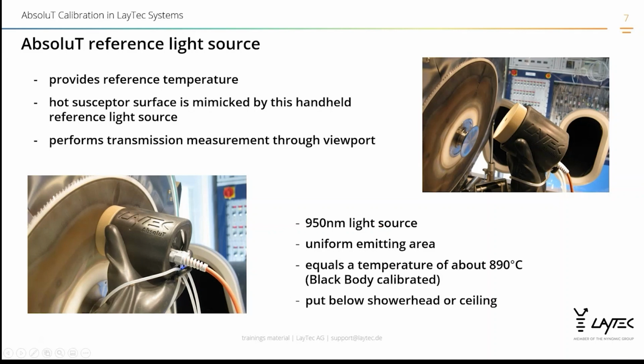We will go in the second part of this video to our test stand lab, and we will demonstrate this live and show all the tips and tricks to perform and prepare this calibration. Here just a quick preview. That is how the front side of the AbsoluT tool looks. There's an exit slit, and that exit slit diameter is much wider than the EpiTT light spot, which passes the ceiling or showerhead viewport tube and is focused to the plane of the wafer. We have to position this exit slit in front of this much smaller EpiTT light spot. And that we will show in the second part. It's basically not that difficult. With a few tries, you will handle this in a minute.